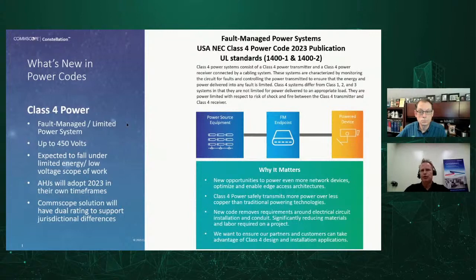Class 4, as I said, is new. The biggest components of this is we're using higher voltage and lower amperage to make it safe and deliver a lot more power than is capable in Class 2. This is expected to fall under low voltage, so low voltage contractors - that really depends on the jurisdiction, and we've seen a mix when we talk to our customers. The Commscope product will have Class 4 certification, which is very important, since certification drives how you can lay the cable.